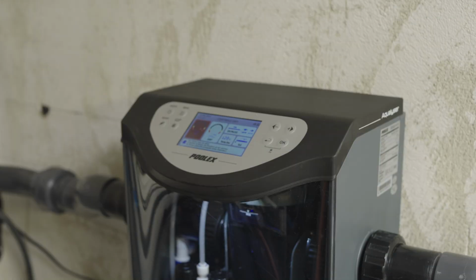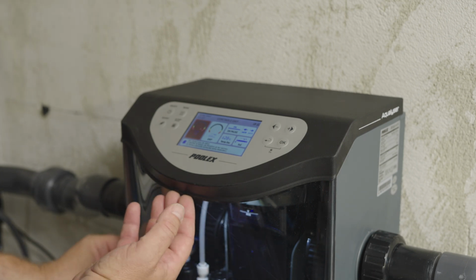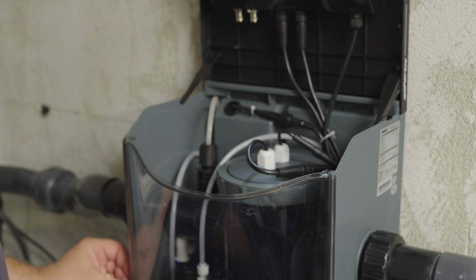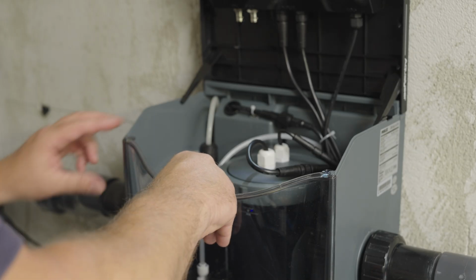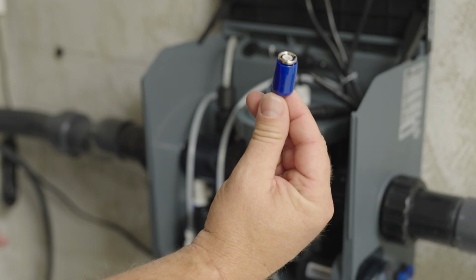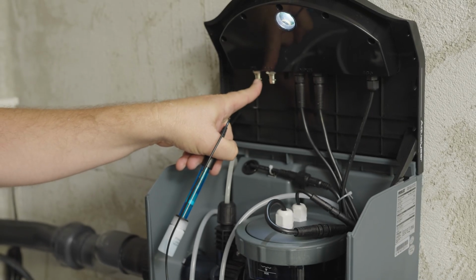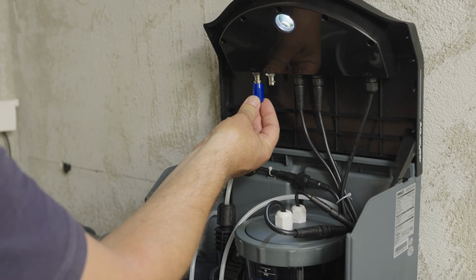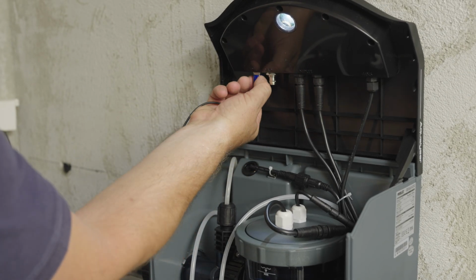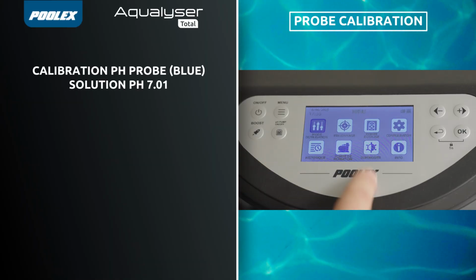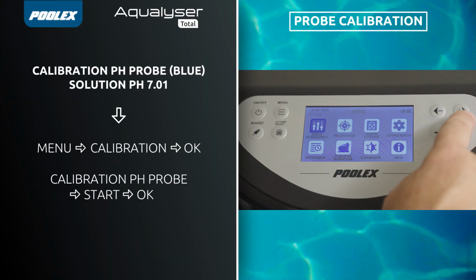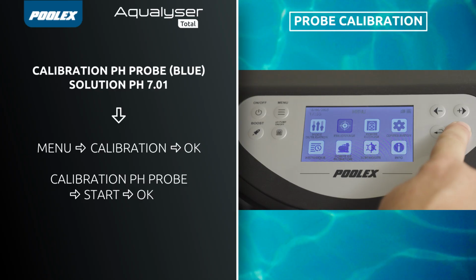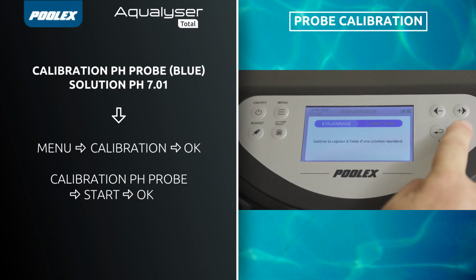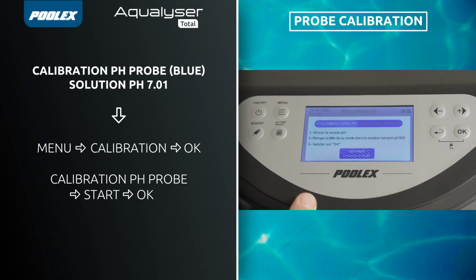To ensure measurement accuracy, it is important to calibrate the probes. To access them, lift the control box and remove the transparent protection on the front. To calibrate, first connect the pH probe to the socket marked pH under the control box. Then, in the menu, use the arrow keys to select Calibration. Choose Calibrate pH Probe. Press Start Calibration.